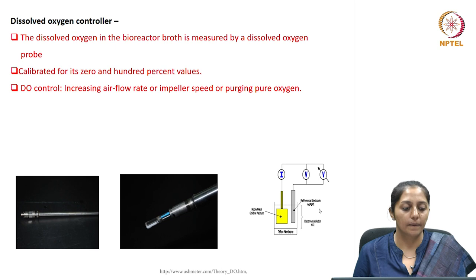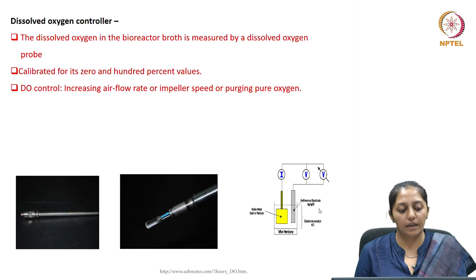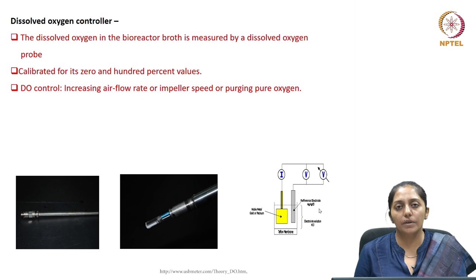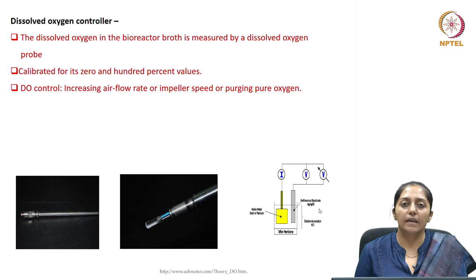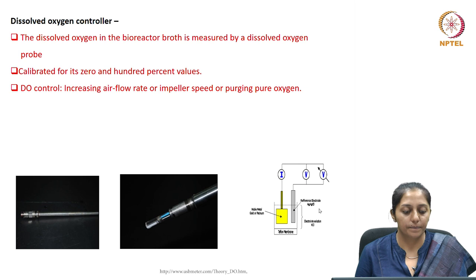The dissolved oxygen in the reactor broth is measured by a dissolved oxygen probe based on galvanic or polarographic electrodes. The polarographic electrode has a membrane at the bottom selectively permeable to oxygen; oxygen gets reduced at the noble metal electrode, causing current flow measured as proportional to the oxygen tension of the broth. For control, the measured signal is compared with the set point, and the error is minimized by increasing the RPM or increasing the air flow rate until the measured value is brought close to the set point.